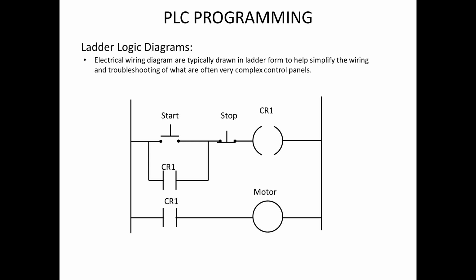a stop push button. And you have to remember, if you look at these wiring diagrams, power goes from left to right. And so when you push that start push button, that will allow power to come across, and it will go through the stop button, and it'll come to this contact relay, and it'll energize that relay. And when that CR1 is energized on the top rung, that bottom rung, which is a match for it, CR1, becomes energized. So once you hit the start push button and complete that circuit, when you let go of that start push button, that circuit maintains contact, so it stays energized.